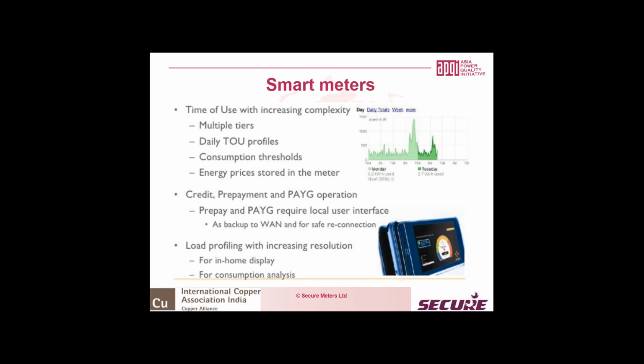In general, smart meters do not talk about power quality, also at the level at which they are supposed to get installed, which is the fag end of the distribution stream, a domestic single phase and three phase consumer. Probably power quality will be too much to ask of smart meters for domestic consumers. So smart meters are a very different ball game. This is more for load management, helping consumers monitor their consumption on a daily basis and bring about energy conservation and optimization, because providing information helps.